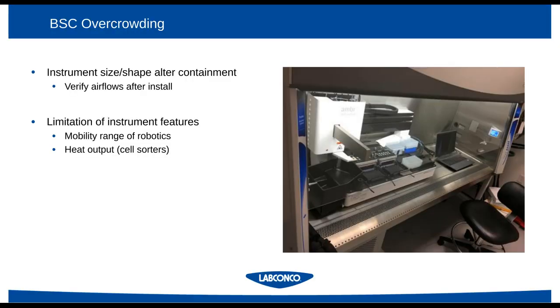Additionally, it's important to look at the limitations that come with robotics inside Class II enclosures. So as you know, there are things like a glass sash that's a protective barrier, and sidewalls that also just ensure the cabinet contains and is robust over its life. But that poses a lot of inherent challenges for robotic systems. So certainly with liquid handlers and other instruments where there's a lot of access requirements to load samples and service, they can be obstructive. And furthermore, on some biosafety cabinets, there are issues with mitigating heat.